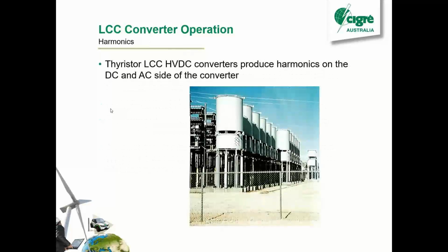The other problem is harmonics. Because we showed the 6-pulse converter before, and we'll go into 12-pulse, but we're not producing perfect sine waves here. So we're going to have harmonics on the DC and the AC side of the converter that we're going to have to filter.